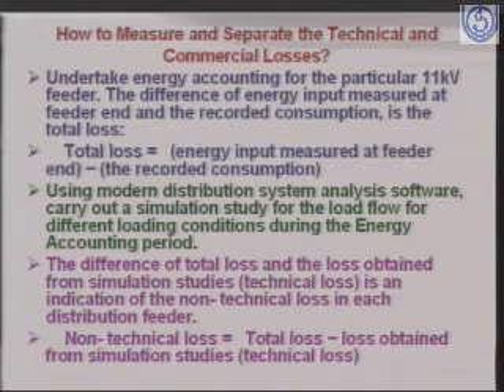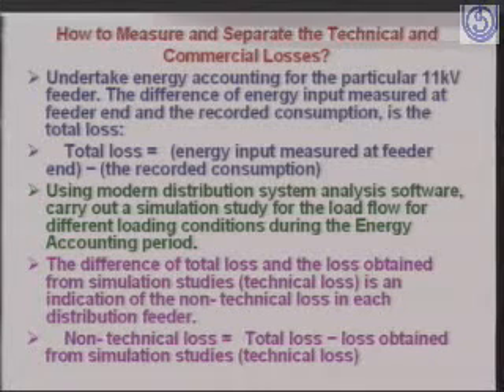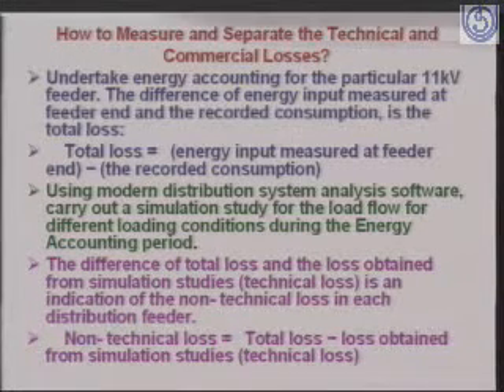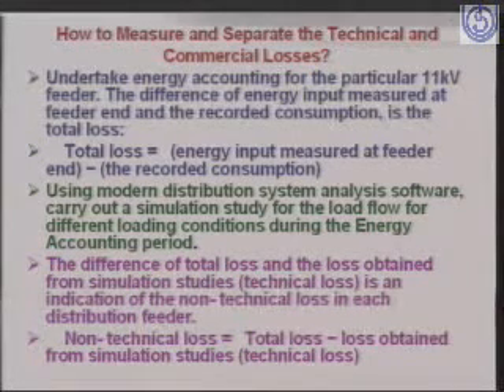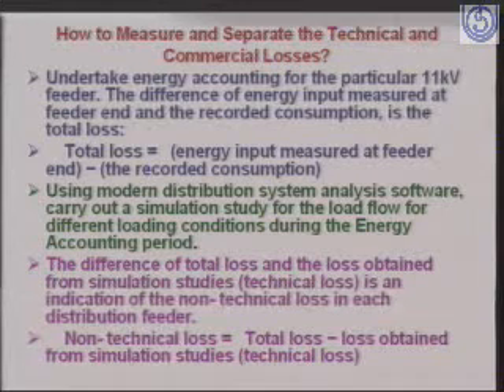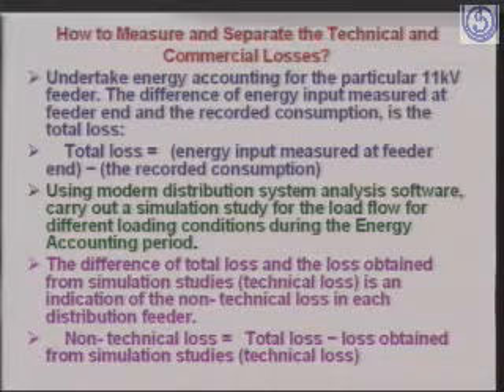Because load is not constant, load is varying with respect to time. Morning demand is different, afternoon demand is different. So the losses will also keep on varying. During peak time the losses are maximum, during lean time the losses are minimum, because we understand that full load losses are proportional to the square of the current which flows. So when the demand is more on the distribution system, the full load copper losses are much higher, in square proportion. So the difference of total loss and the loss obtained from simulation studies is an indicator of the non-technical losses in each distribution feeder. Non-technical losses are total loss minus loss obtained from simulation studies.